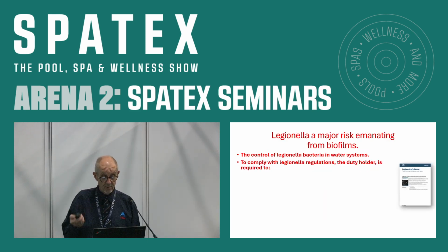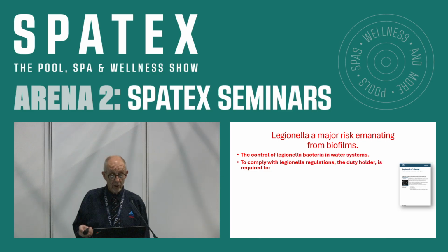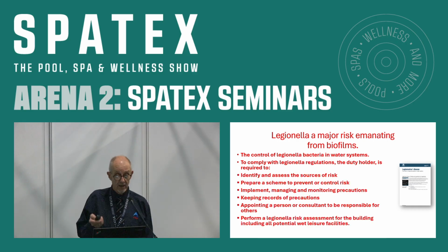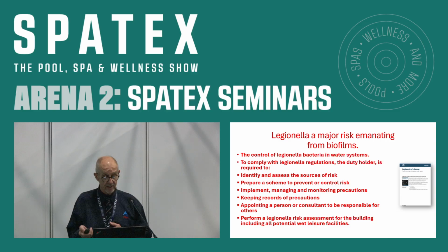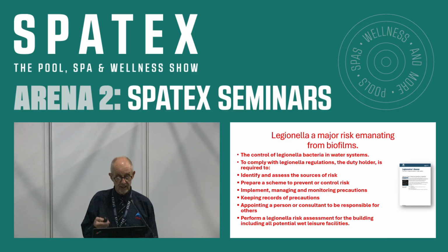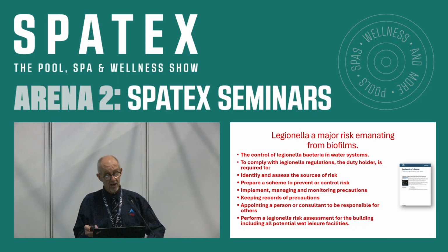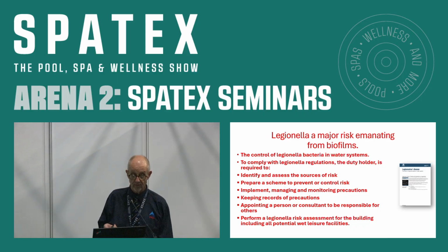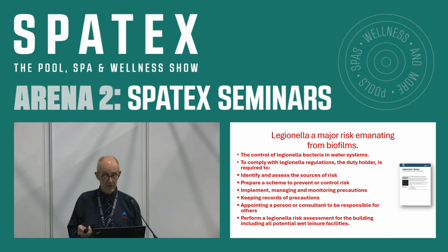Legionella major risk emanating from biofilms. Control of Legionella bacteria in water systems, L8. To comply with Legionella regulations, a duty holder is required to identify and assess the risk, prepare a scheme to prevent and control the risk. This is a legal requirement. Implement, manage and monitor precautions, keep records of precautions and reactions, appoint a person or consultant to be responsible for others, perform a Legionella risk assessment for the building, including all potential wet leisure facilities.